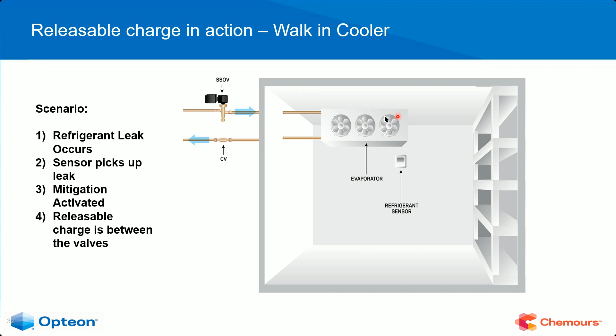All right. And in this mitigation strategy, the releasable charge is in between the 2 valves. So in other words, when it senses the leak, the mitigation is activated. It could be one of 2 things. First thing we're going to do, though, in these walk-in cooler type applications, is shut this down. The solenoid's going to close, and the check valve's in place so nothing can come back in there. Between these two is what's considered releasable charge. And how much of that depends on what type of application it is, as we talked about earlier. Are you just going to need the evaporator fans to kick on for moving air? Or are we going to need to bring in fresh air or move air in? That's going to depend on the strategy.